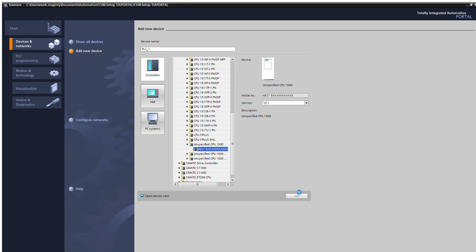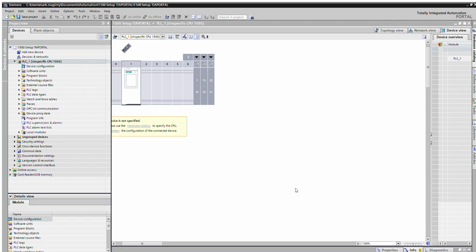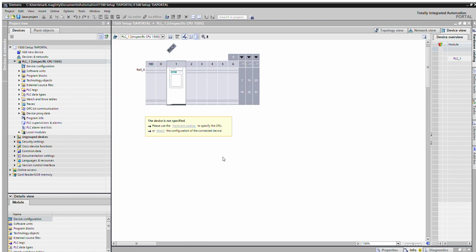That's now going to make the software find out, via the network, what it's connected to, rather than having to tell it. On this particular page, we are in the device setup and we can press the detect option here, which is the easiest method. You need to then go via your Ethernet, which is how I'm connected, and hit start search. Mine finds quite a few controllers that are available within the room at the minute, and the one I particularly want is this 10.100, which is sitting just up behind me, so I can flash the LED. I can make sure the LEDs flash, which they are, so I'm guaranteed that that's the correct one I want.